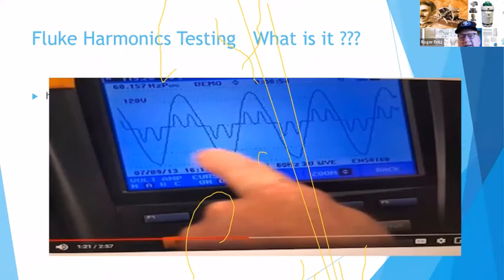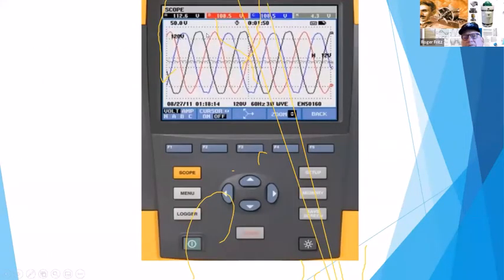So what we're talking about is it gives us the scoping capability to look at that voltage waveform, the actual current waveforms, and you'll actually see these pulse ripples going into a VFD. And from that, you can then get the overall view, and you're able to even see the effect of the harmonics that happen inside. You'll see the effects on the waveforms, which are very key, because the cleaner we keep it back to the original waveform that Nikola Tesla had in mind, and the cleaner we keep that to the motor itself, the happier it becomes.